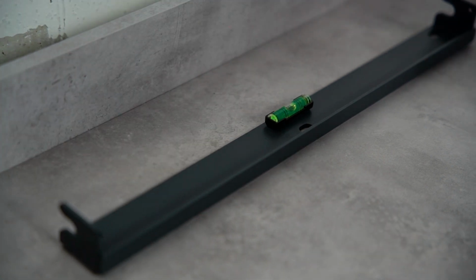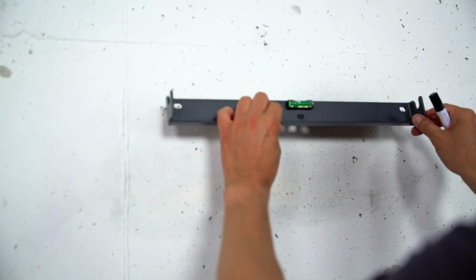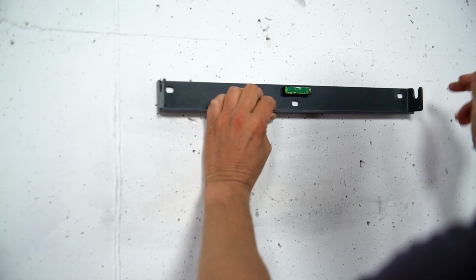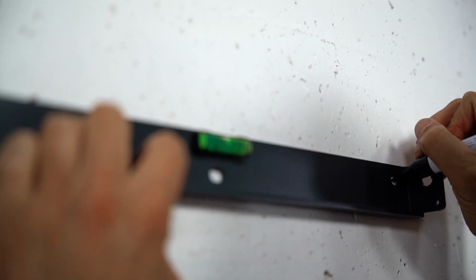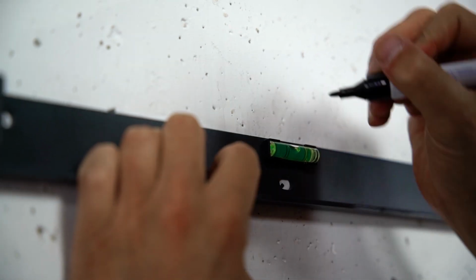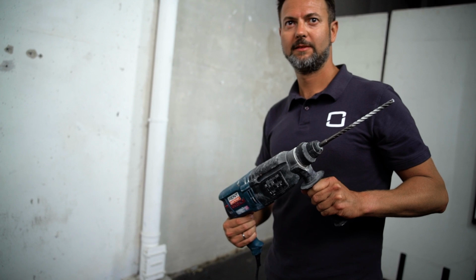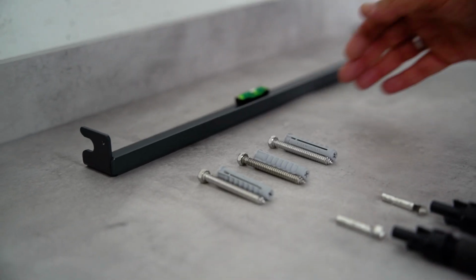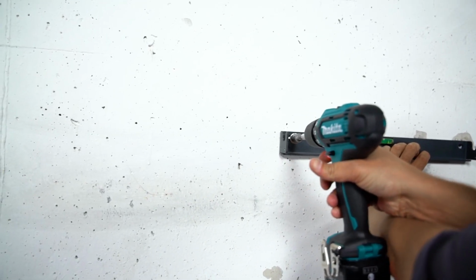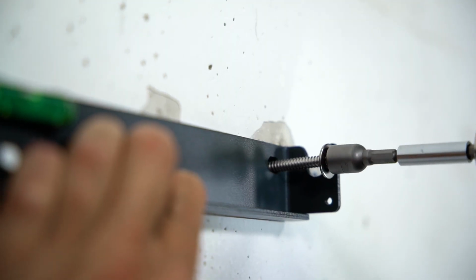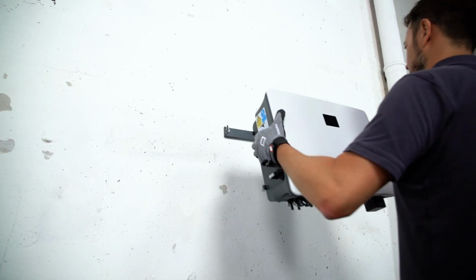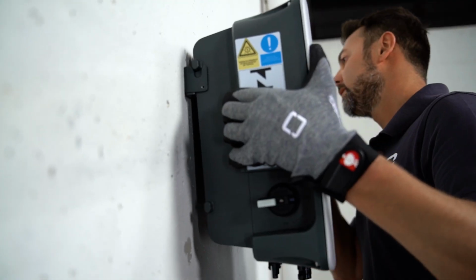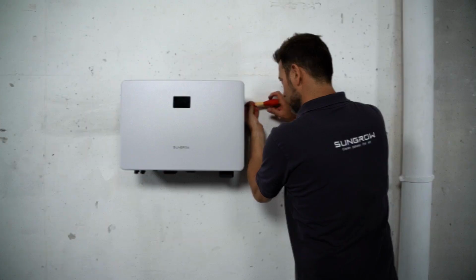And off we go! Luckily, you don't need a spirit level. Sungrow has it integrated in the mounting plate. Before you start drilling, you should make sure that there are no wires running through the wall that you could damage. Take your drill with a 10 mm drill bit and drill at least 70 mm deep into the wall at the marked points. The dowels for mounting the inverter on the wall are included in the delivery. You will also need a cordless screwdriver for attaching the mounting plate. The required screws are part of the delivery. For the lift-out protection, you need a cross screwdriver to fix the two M4 fixing screws and washers.